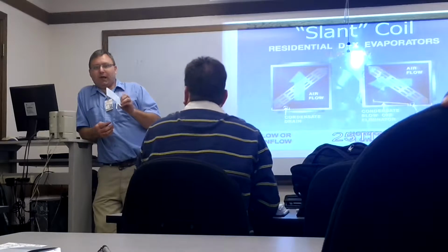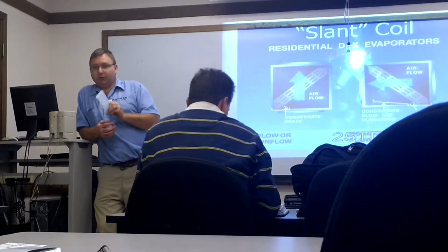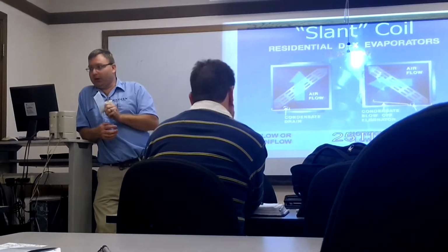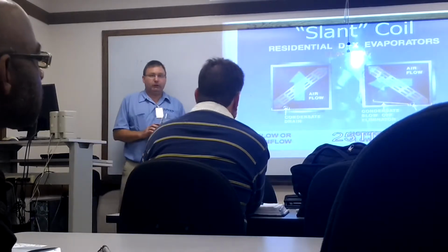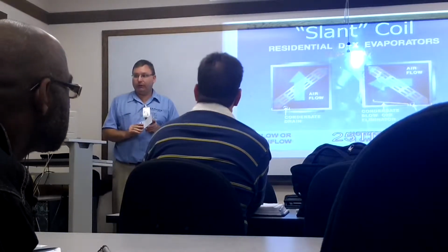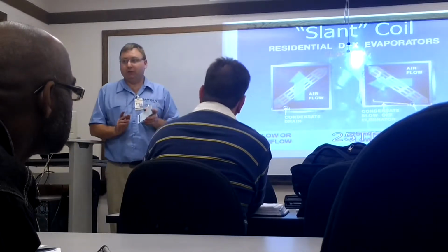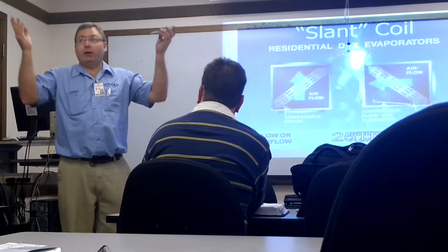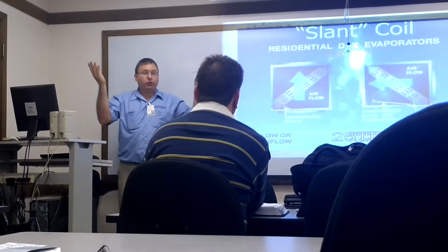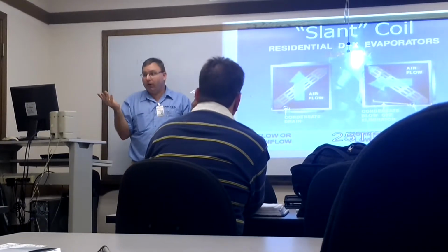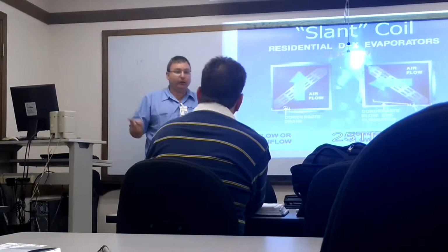That's right. So anytime that we've got our evaporator coil on the negative side of the blower. Right. So if the evaporator coil is on the return side of the blower, you've always got to put a trap on. And I can't tell you how many cases I've worked on out in the field where the guys don't have traps on there, and the unit will work just fine, except it rains water every time the unit shuts off. That's because the trap is either missing, because somebody didn't put it on, or it's got a crack in it. And that's very common when you're coming out of winter and going into spring.